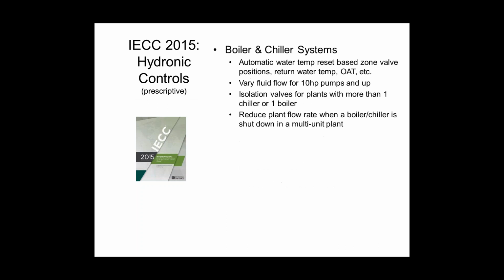Hydronic systems, from a controls perspective, boilers and chillers, there's a few things that you definitely have to do as well. You have to have a means of automatic water temperature reset based on something. They give you lots of choices of the something. Zone valve positions is one such way. You can do it based on return water temperature. You can do it based on outside air. And there's a few other things they'll let you do as well. But you've got to have something that resets the temperature so you're not always providing 45-degree water. Something has to bump it up to 46 or 47 or 48 or whatever it is.